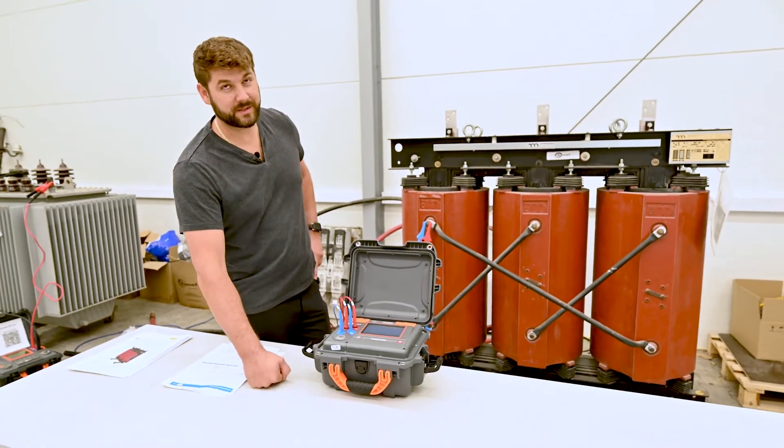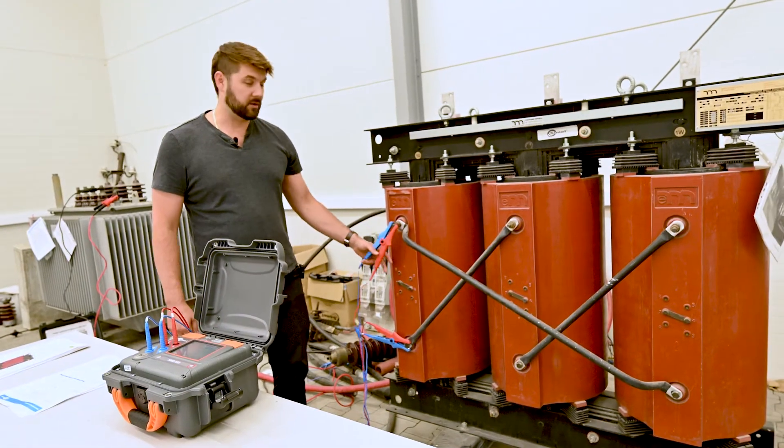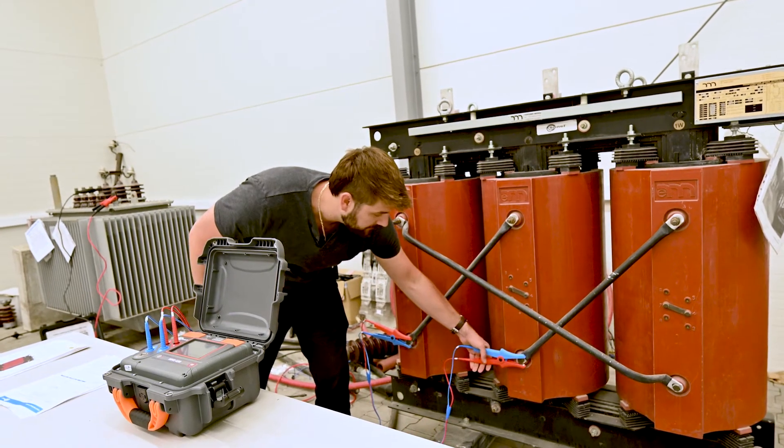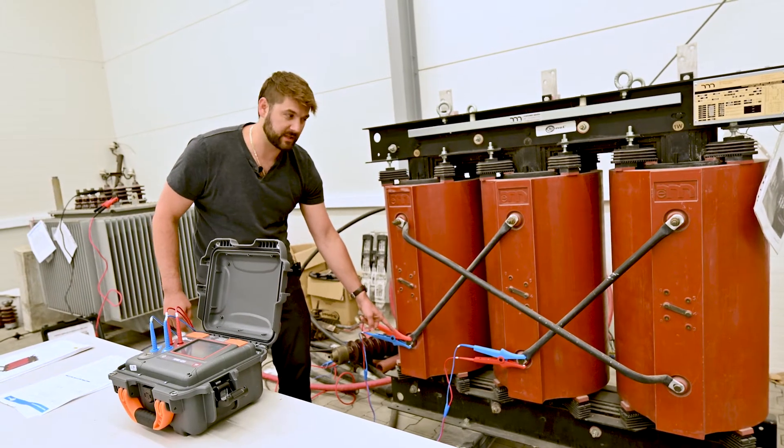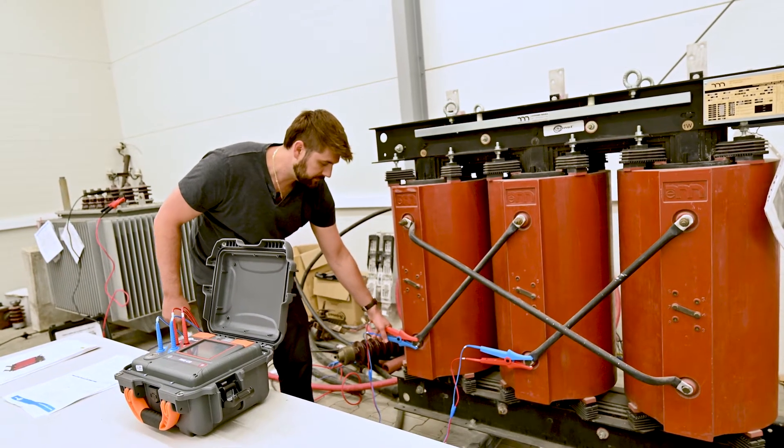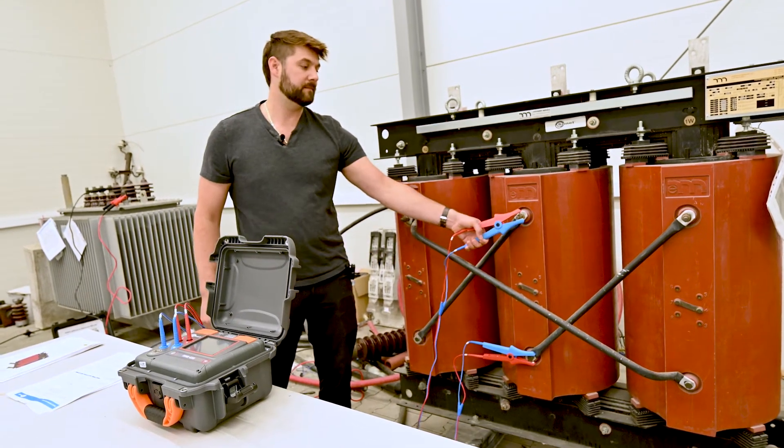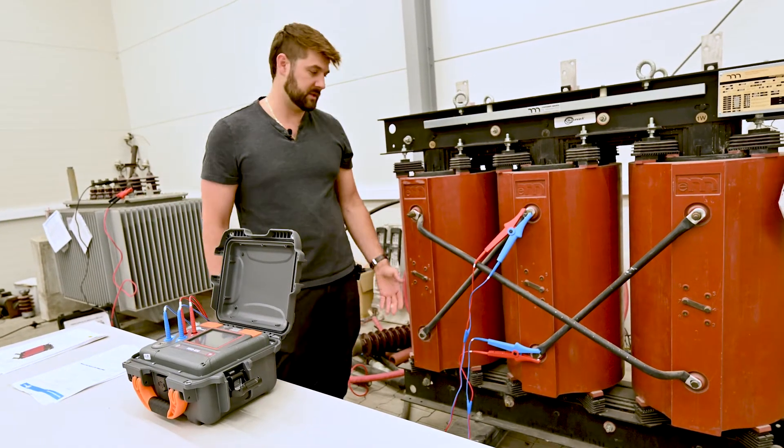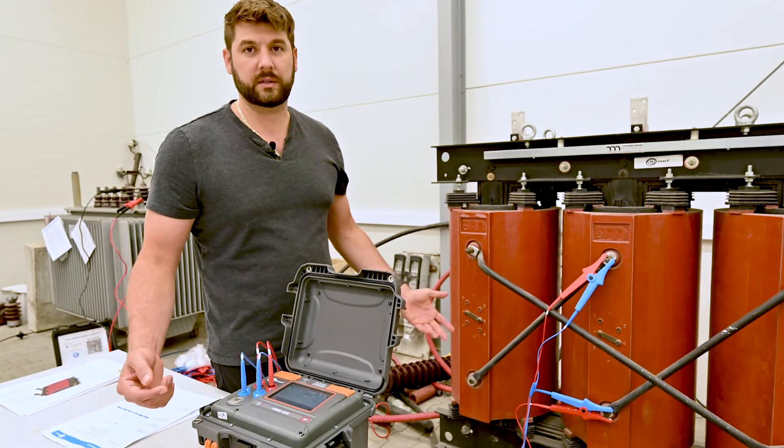Okay, 7.6 ohms. Going to go to the next phase. All I need to do is move this lead to here. We're going across this winding now. I can leave this here and I will include this bar in the measurement, but if I put it here, we exclude the bar. The bar has very low resistance compared to the winding, so either location is fine.